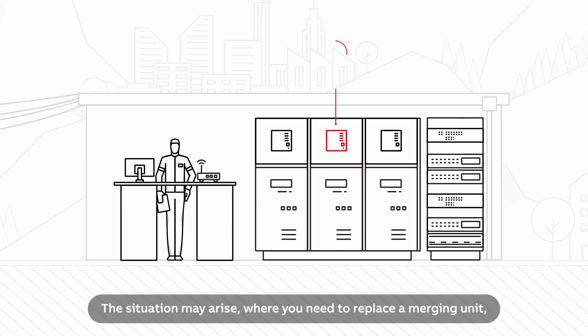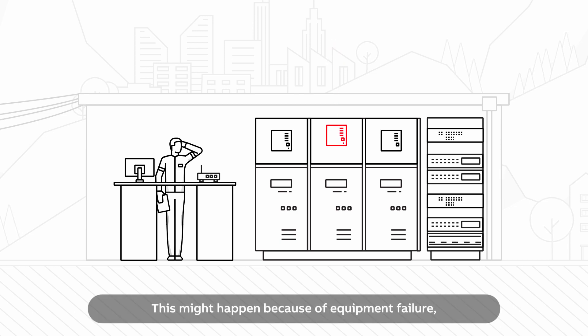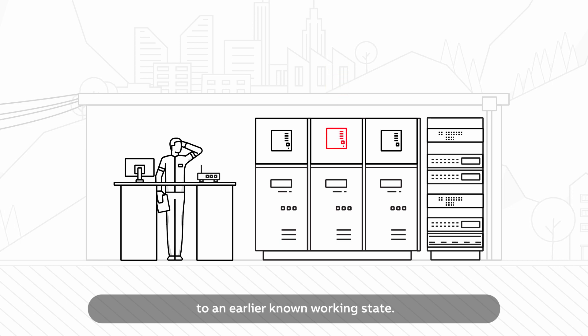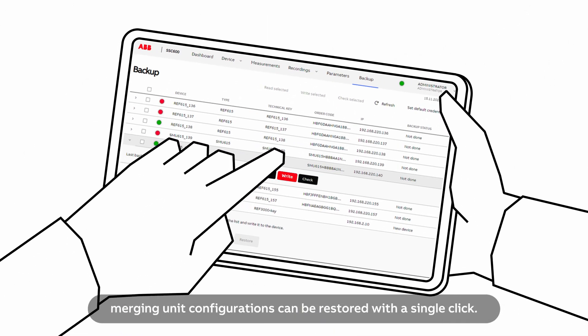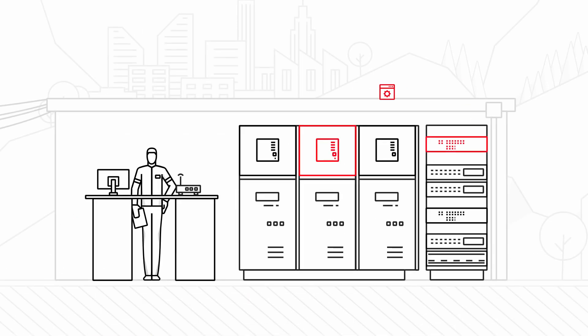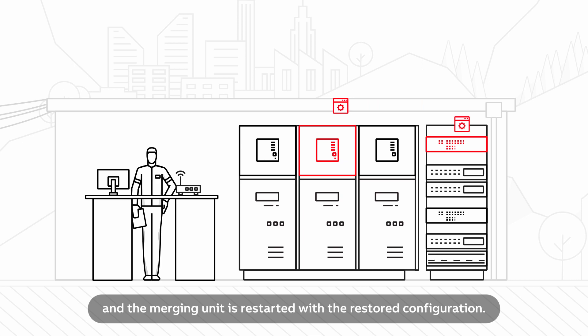The situation may arise where you need to replace a merging unit or you need to restore the configuration to an earlier state. This might happen because of equipment failure or when you need to restore the system to an earlier known working state. With a centralized approach, merging unit configurations can be restored with a single click. Simply use the SSC600 Web HMI's backup view. SSC600 then automatically ensures that the configuration is written correctly and the merging unit is restarted with the restored configuration.